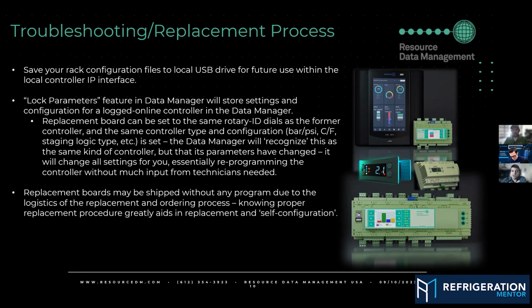They need to make sure it's set for the right control type, which you can do through the front buttons too. So you can set it for either a cold room type or a case type. Then you're going to want to make sure your probe and your pressure units are set. So if you're using 10K2 and PSI, you're going to want to make sure that's set. And then set your controller ID or your rotary dials. That basically tells the data manager that this is the same controller, even though it's a brand new one. And then when all of it comes back up and the data manager recognizes that its settings have changed, it will say, hey, I have all your settings here, and it'll dump them back in. And then at that point, if you did it right, you can walk away from it. It's done. It's already pre-configured itself.